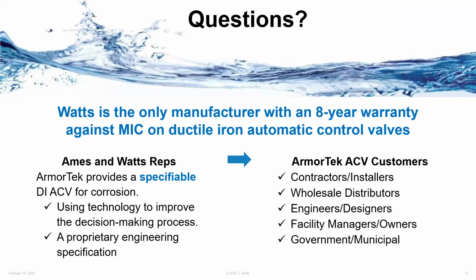No, mainly everybody has, as you said, a warranty on parts for 3 years, all the manufacturers, including us. We are the only manufacturer, though, putting an 8-year warranty against MIC on ductile iron control valves. We are the only manufacturer in the industry doing this. And you say, well why? Because this isn't something we came up with yesterday. We've been field testing this for over, I'll say 6 years now, before we actually introduced this into the marketplace. So we've been doing a tremendous amount of field testing. If you take the program itself, it's close to 8 years. Watts has been working on this to bring it to commercialization. So right now, we are the only manufacturer offering this.